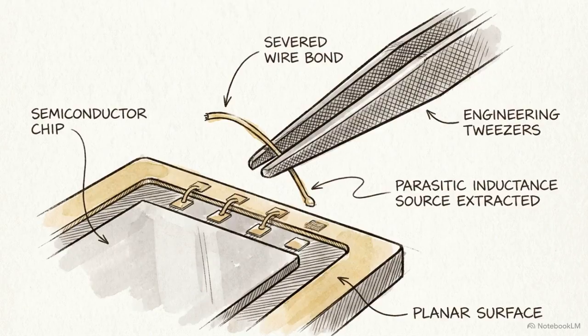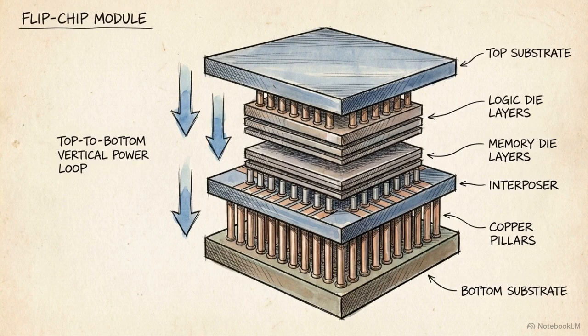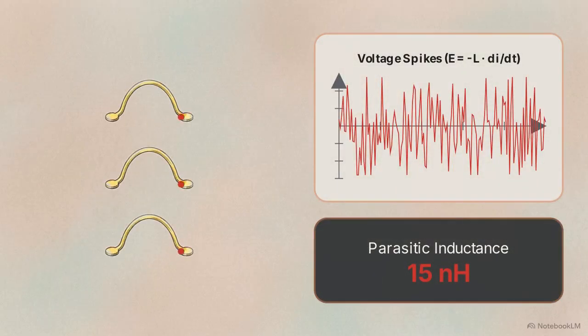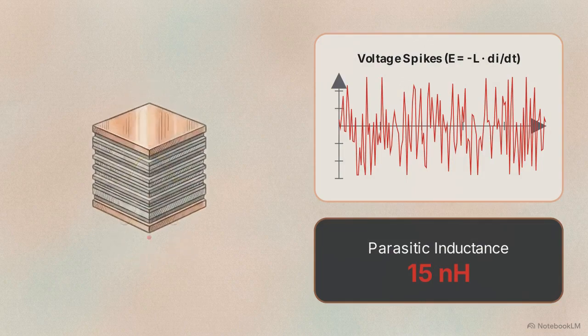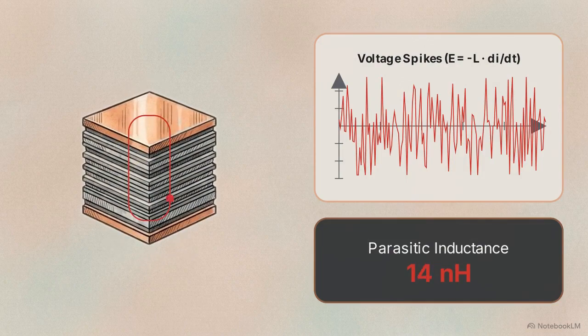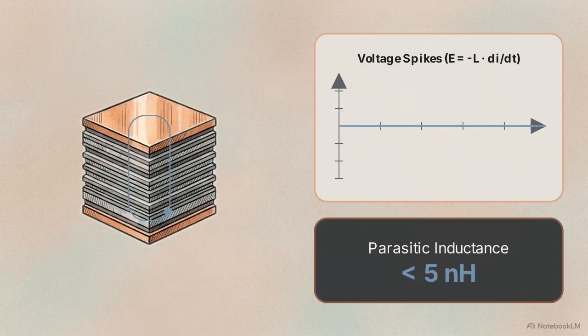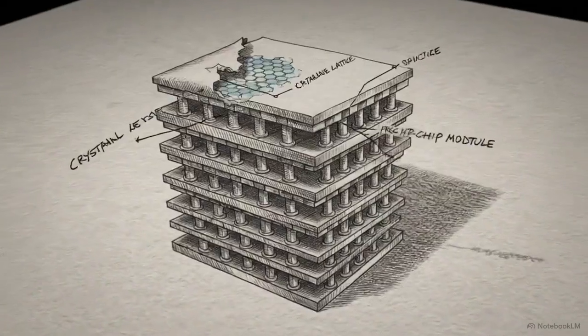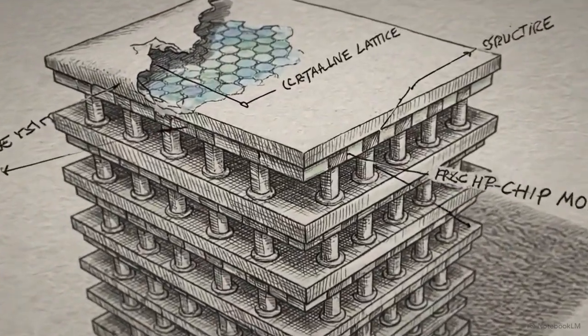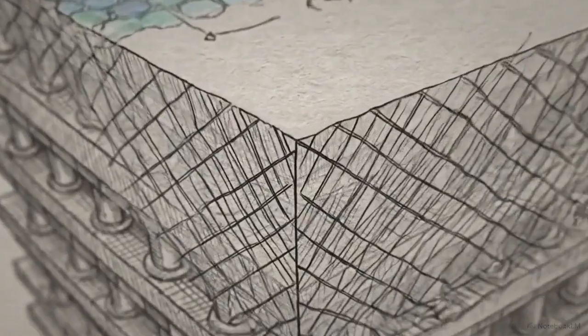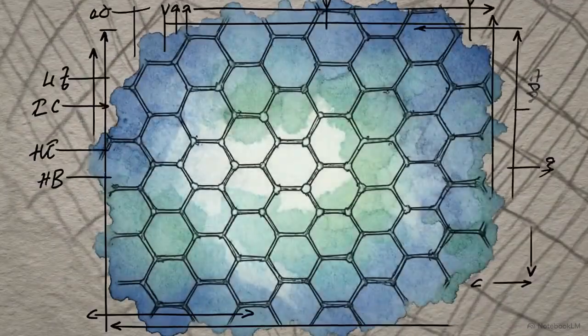Engineers are abandoning legacy planar packaging. They are stripping out the problematic wire bonds entirely in favor of wire bondless, flip-chip modules designed with tight, three-dimensional vertical power loops. This geometric redesign has a massive impact. By shortening the physical circuit paths, parasitic inductance plummets from 15 nanohenries down to less than 5, mathematically flattening out the destructive voltage spikes. In the era of silicon carbide, physical geometry and proximity of connections are just as critical to performance as the semiconductor's chemistry itself.